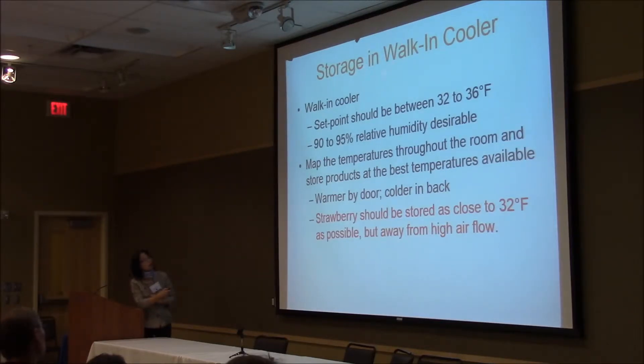For storage in a walk-in cooler, the set point should be between 32 to 36°F — you want to keep strawberries as close to 0 to 2 degrees C as possible for extending shelf life. Also, retain higher relative humidity of 90 to 95% to prevent transpiration and retain water in the strawberries. You also want to map the temperature throughout the room and store products at the best temperature available. Don't assume all points in a cold storage room are the same temperature — that's not true. You want to ensure uniform temperature in the cold room and avoid hot or cold spots to prevent warming or over-cooling.